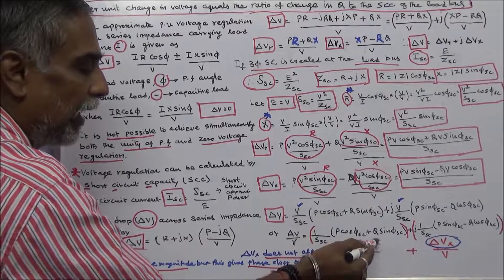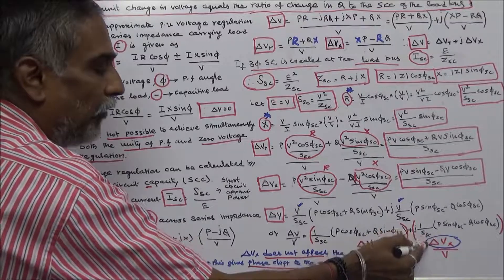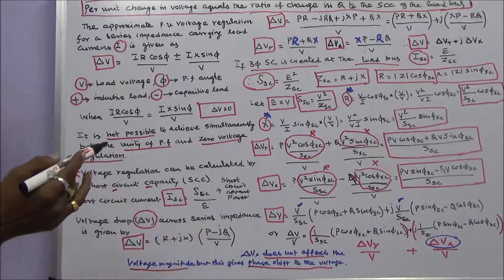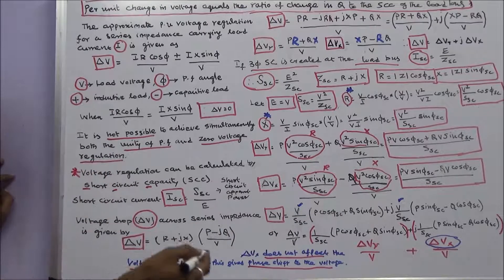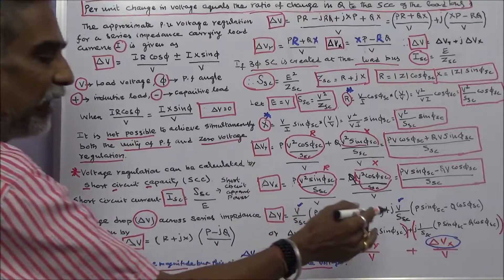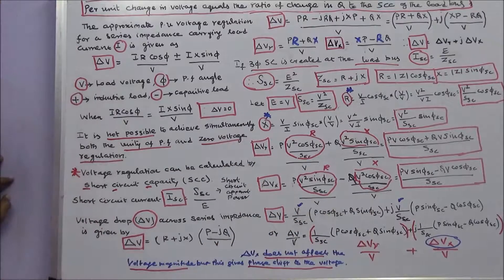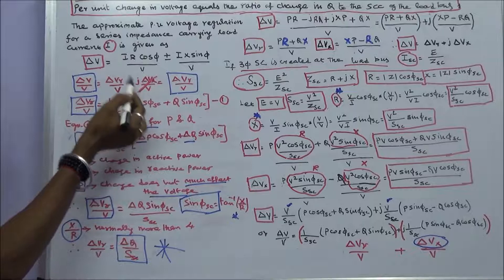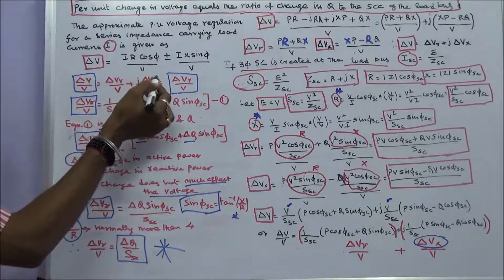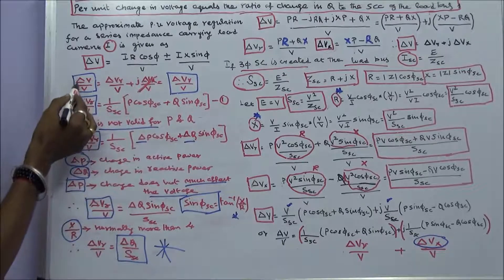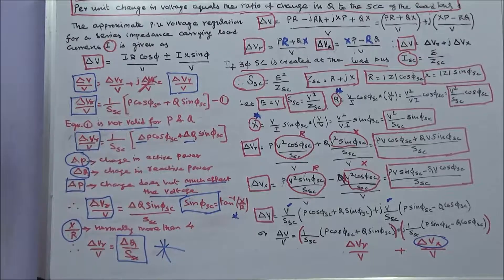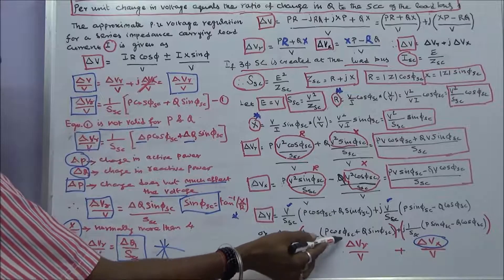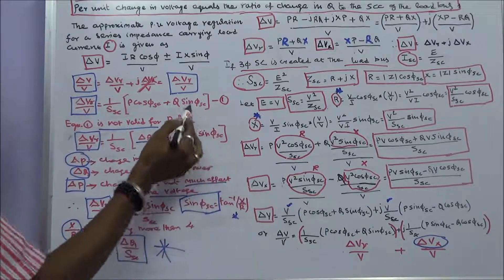We can write delta V / V equals delta V_R / V plus j·delta V_X / V. The imaginary component delta V_X does not affect the voltage magnitude — it only causes a phase shift in the voltage. Hence, we neglect it. Therefore, delta V / V equals delta V_R / V, which equals 1 divided by S_SC times [P·cos(φ_SC) plus Q·sin(φ_SC)]. This is Equation 1.